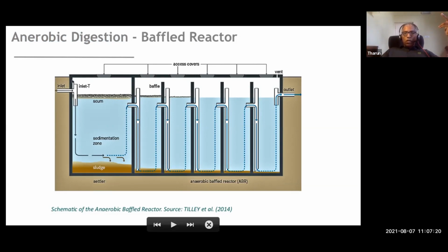So all the fecal matter flushed down comes into a tank. It's nothing like a septic tank. It comes in here, then it goes to multiple small partitions, multiple baffles. You go up, go down, up and down. Any anaerobic technology, more or less, is a similar concept. Like I said, in aerobic you have air blowing through fecal matter. Here it goes in, a scum layer is formed, and it gets treated. The bacteria disintegrate everything, like I said, the 4 sets of bacteria come in, and clear water comes out, and you can have multiple boxes like this.